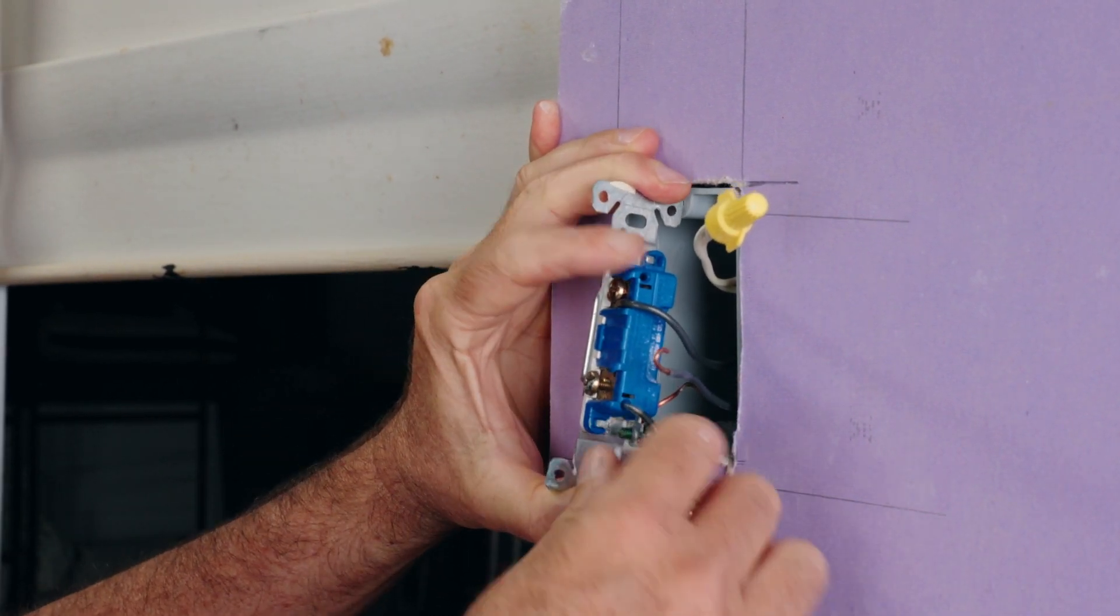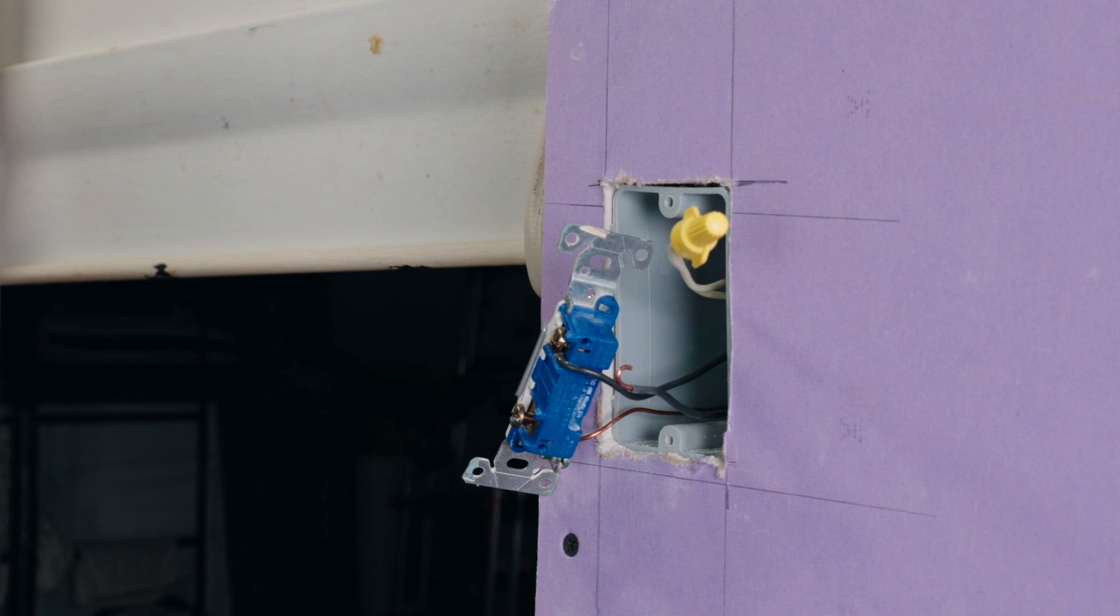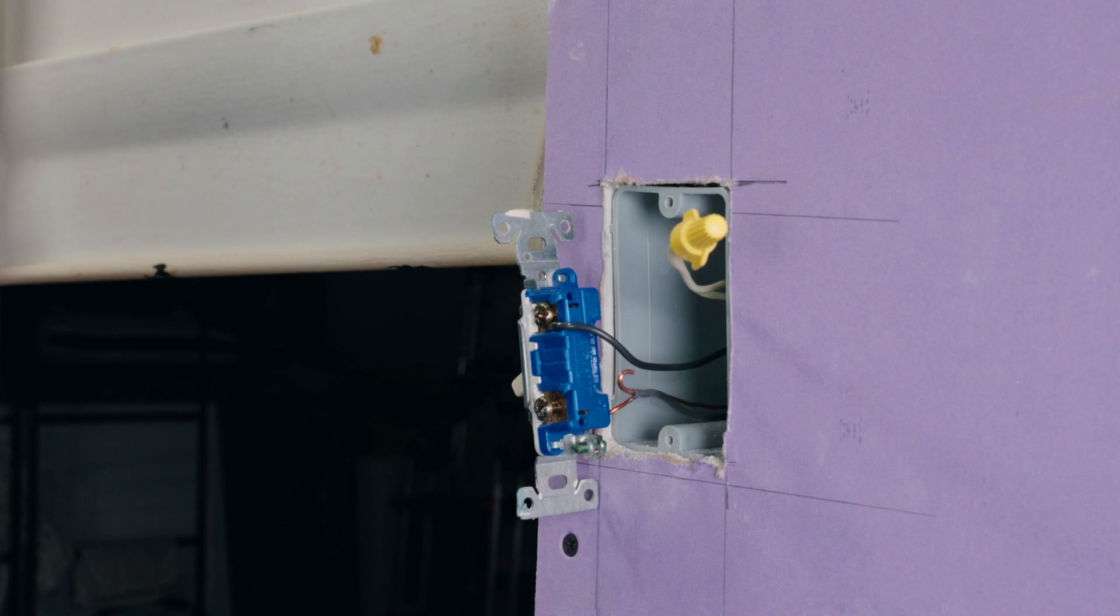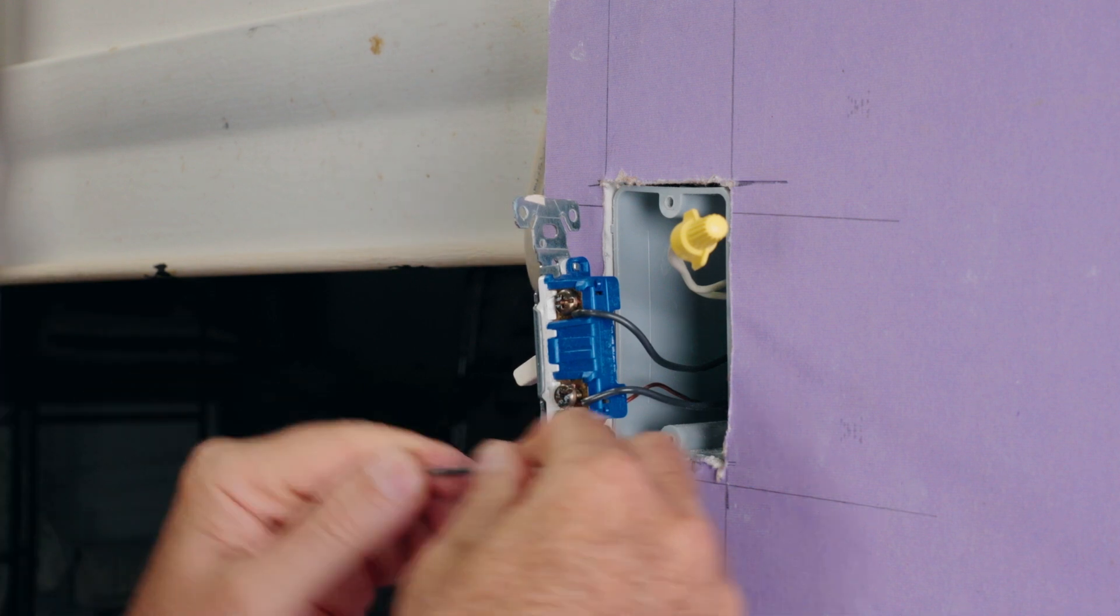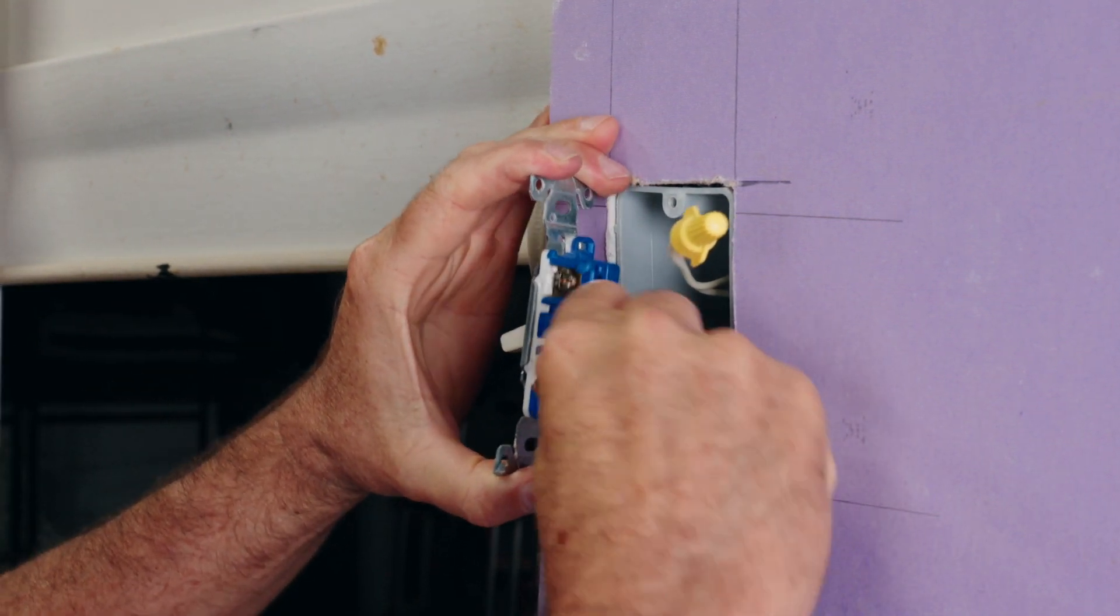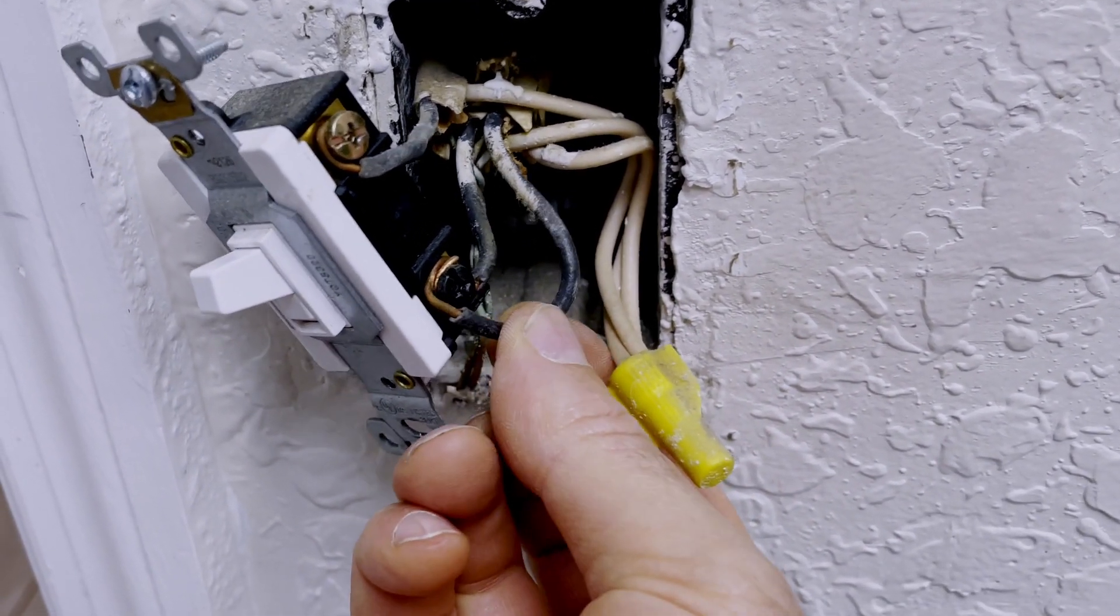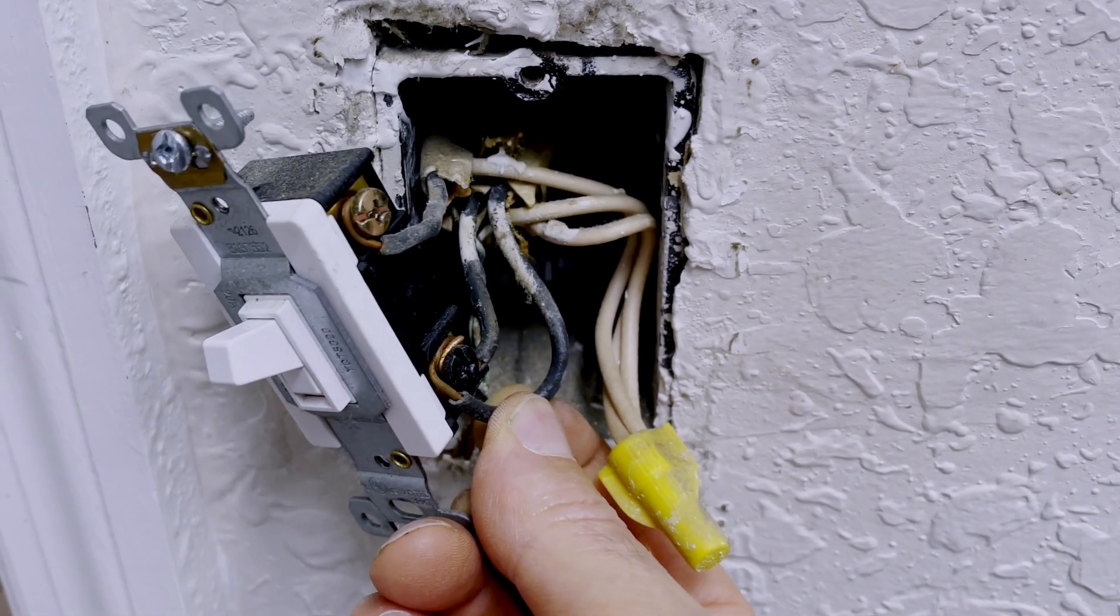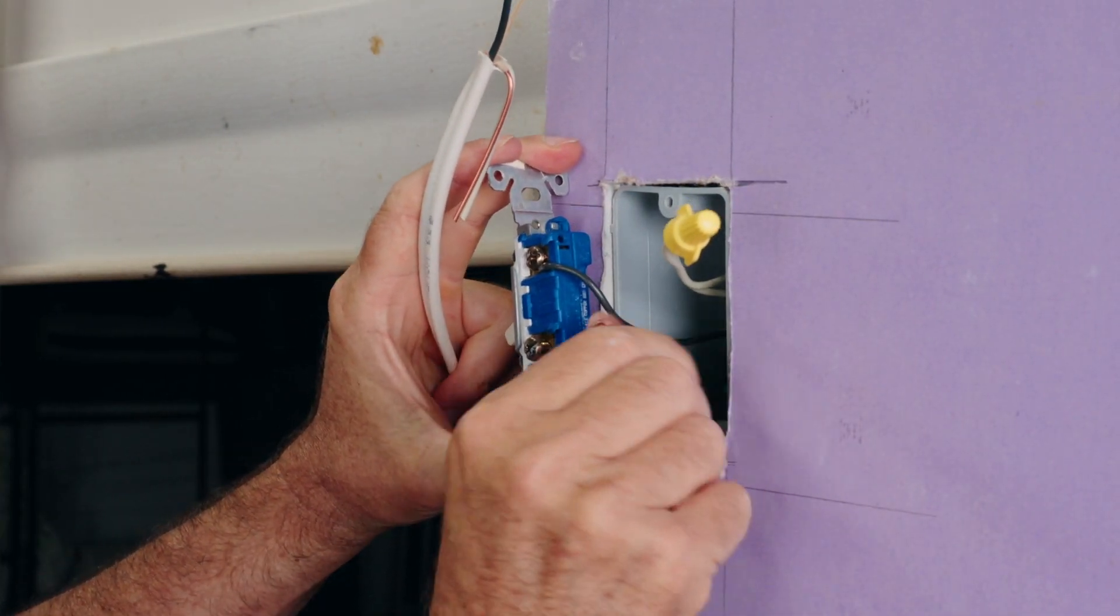Over time, they can come loose and cause a high resistance connection. Or you might be tempted to just put another one in there right on top of it and tighten up the screw. Here's a live shot of one that I actually found that was like this and it was causing some problems because over time it came loose. These aren't designed to do that. Don't do it that way. Take this off and we're going to make a pigtail.